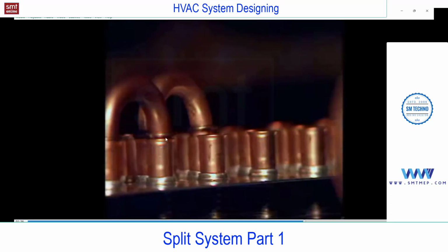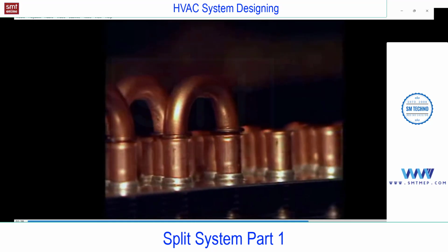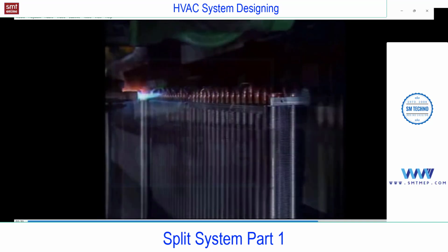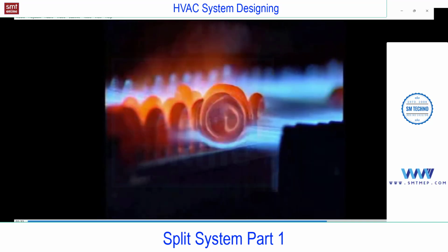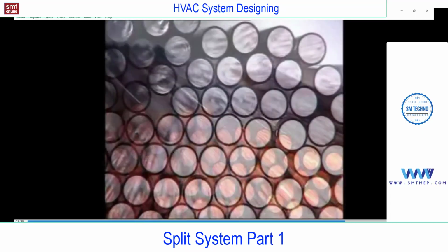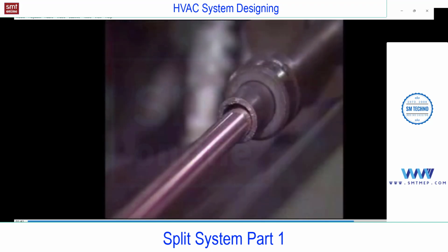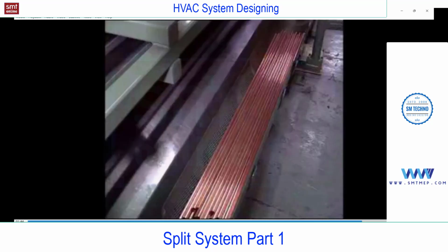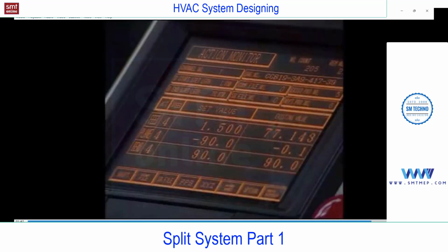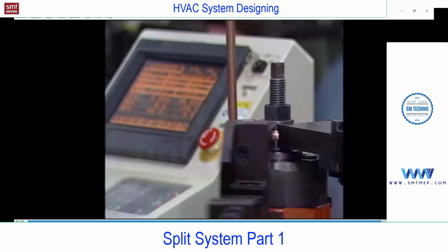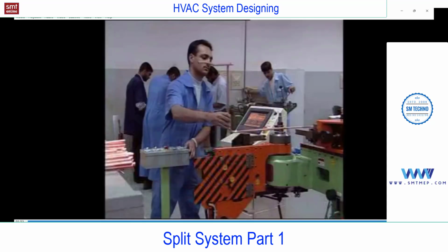Loaded onto the brazing conveyor, you see here we'll apply heat, and this process is called brazing. So to complete the circuit, coils are fitted with elbows and brazing rings. After pressurization, coils move over to the automatic brazing furnace for leak-free connections. Connecting the various air conditioning components requires accurately bent copper tubes. Utilizing CNC three-dimensional copper tube bending machines that conform to the hundreds of various coil connections permits error and defect-free production of volume and quality.